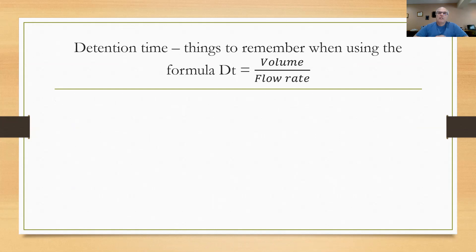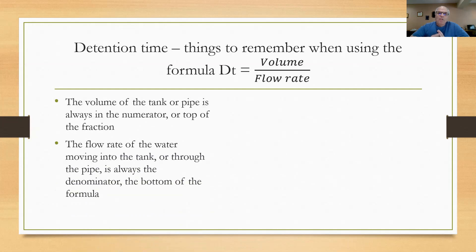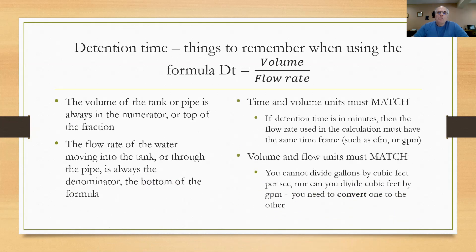Now here's some things that you should remember when you're doing a detention time calculation. When you're using the formula of detention time equals volume divided by flow rate, first of all, the volume of the tank or the pipe or the vessel that you're filling or emptying is always going to be on the top of the fraction, the numerator. The flow rate, the amount of water that you're taking in or out of the vessel always goes in the denominator or the bottom of the formula. Some other important things that you need to remember is that the time and volume units must match. If they're asking you detention time in minutes, then the flow rate that you use has to be converted to cubic feet per minute or gallons per minute. And maybe more importantly, the volume and flow units have to match too. You cannot divide gallons by cubic feet per second, nor can you divide cubic feet by gallons per minute. You need to convert one or the other.